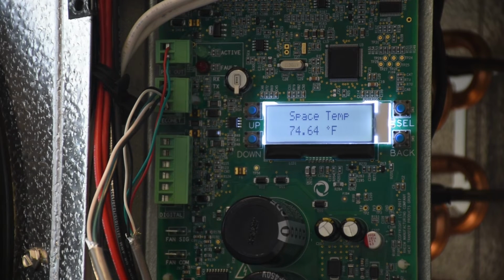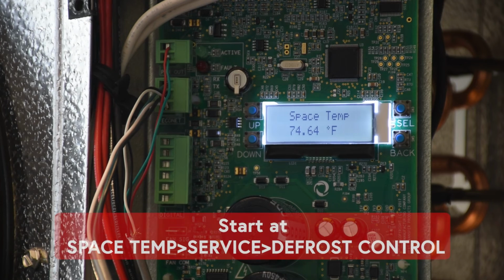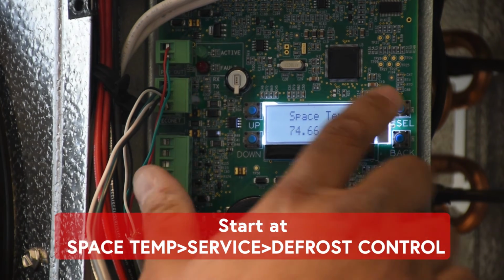So one more thing to consider with the defrost on the controller is how to manually force a defrost. This is done if there's still some time remaining on the runtime counter, and you need a defrost right now. So you can just bypass that and manually force a defrost at the controller, and that is done through the service screen.